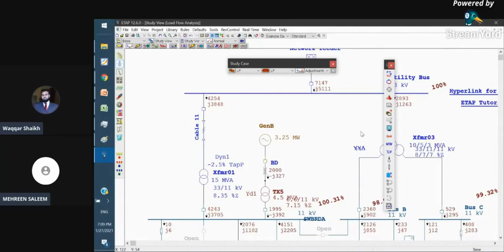There is one deficiency in ETAP software, I would say, that it does not give you an indication of oversizing. If a transformer is 100% loaded or more than 95% loaded, it will give you an alert, critical or marginal. But if the transformer is considered as double sized, like the running load flows give you 100 kVA and the transformer is rated 500 kVA, it will not give you any indication.